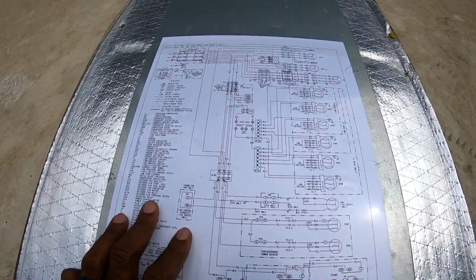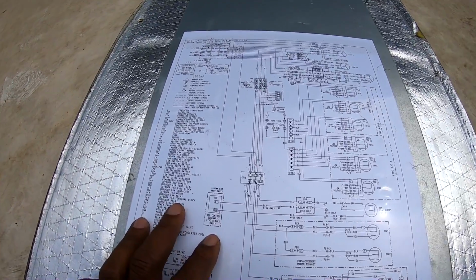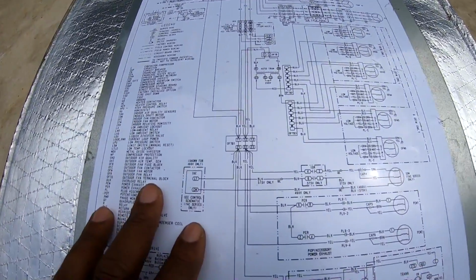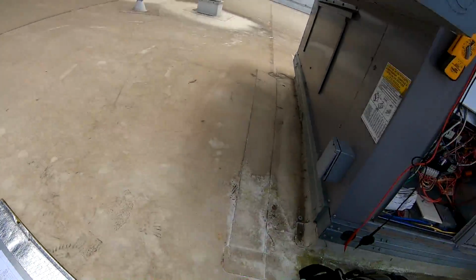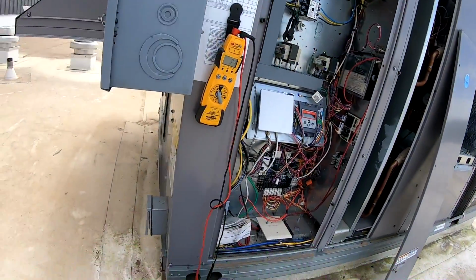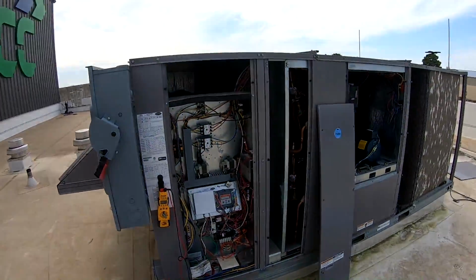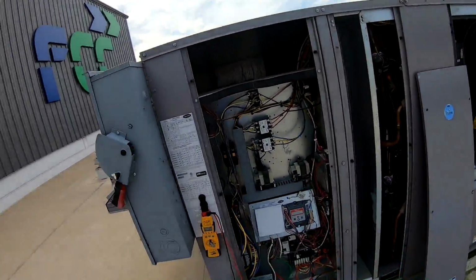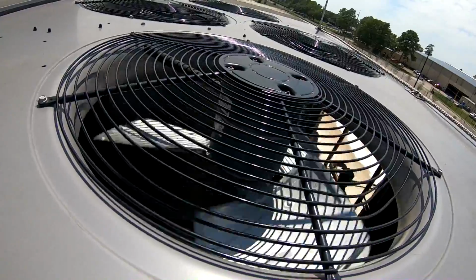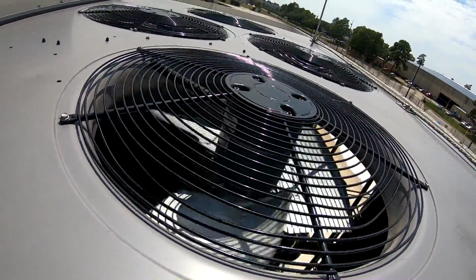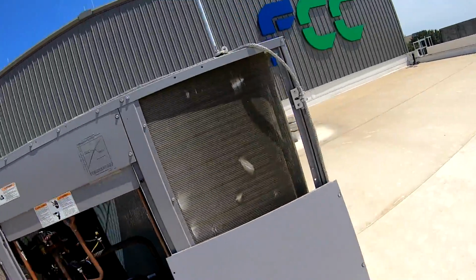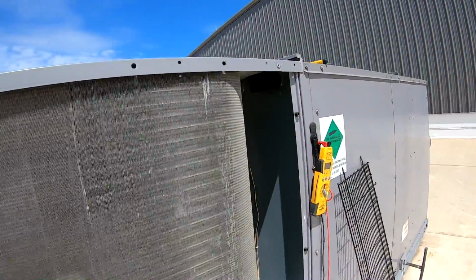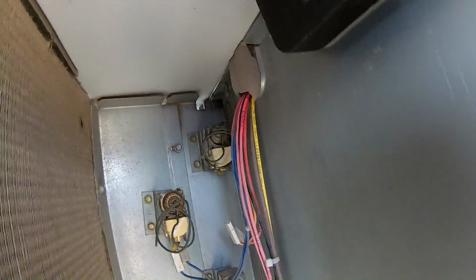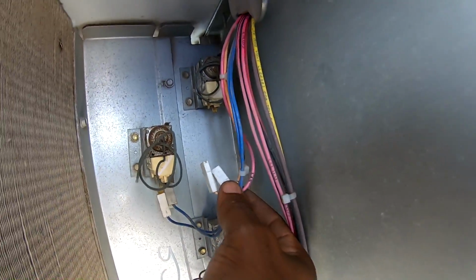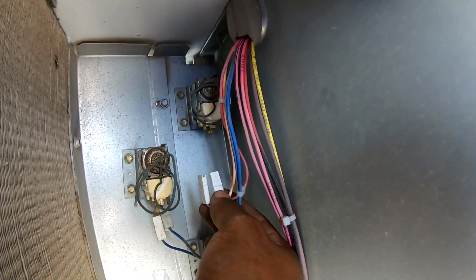I don't think it's the fan itself, because usually all of them don't go out at one time. We may have a fuse problem, but I doubt it, because none of them are really turning. So I'm gonna track down the relays and the fuse blocks. As you can see, probably hard to tell with the camera, but the fans are running now. I had troubleshot it because it was going off on the high pressure switch, but it has a low ambient switch right here that's locking this unit out. So that low ambient switch needs to be replaced.